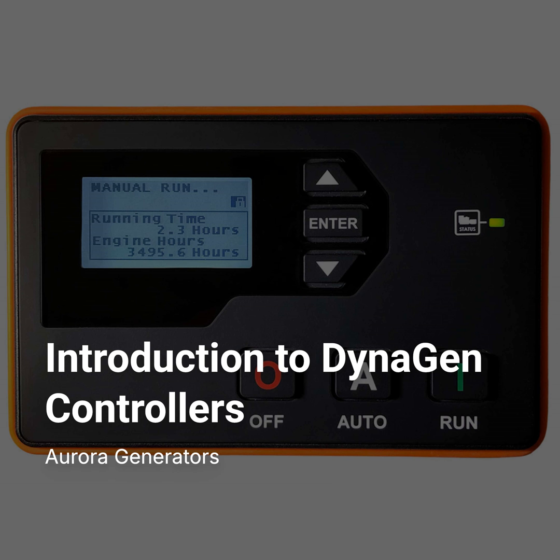Right. There are also settings for handling things like false starts, where the engine fires briefly and then stalls, and false checks to avoid misinterpreting brief glitches. Those false start settings sound useful, they prevent nuisance stops. What about more proactive scheduled stuff? They include an exerciser function that lets you schedule automatic engine exercise periods. For standby generators. Exactly. Typically set up maybe 16 weekly events, with configurable start time and run duration. It keeps standby units tested and ready.